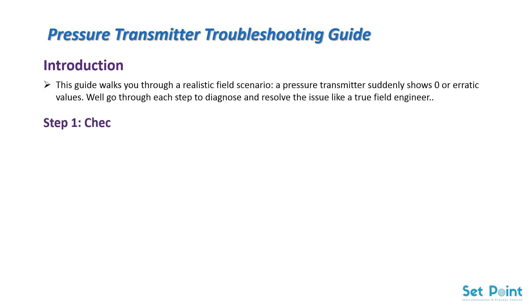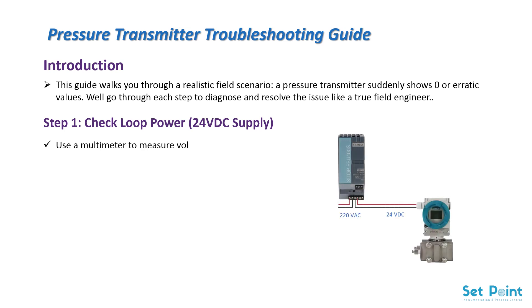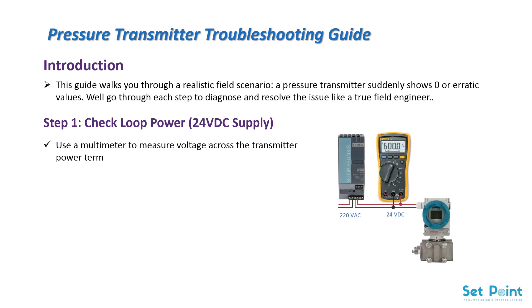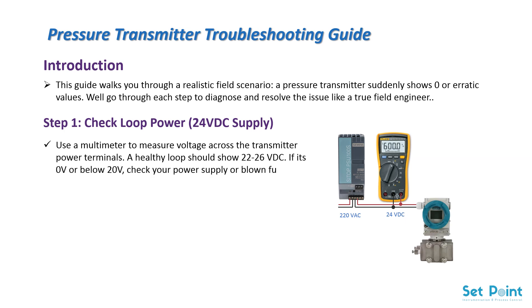Step 1: Check loop power — 24 volt DC supply. Use a multimeter to measure voltage across the transmitter power terminals. A healthy loop should show 22 to 26 volt DC. If it's 0 volt or below 20 volt, check your power supply or blown fuses.